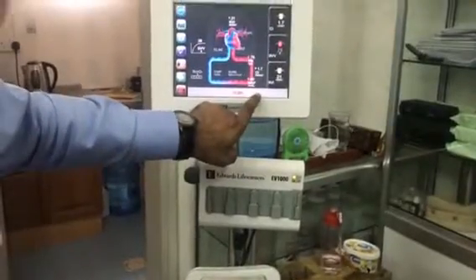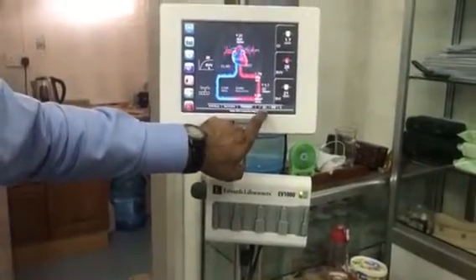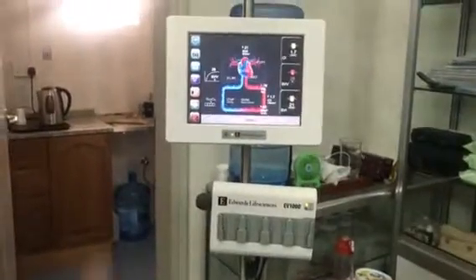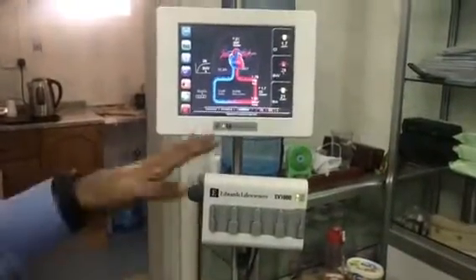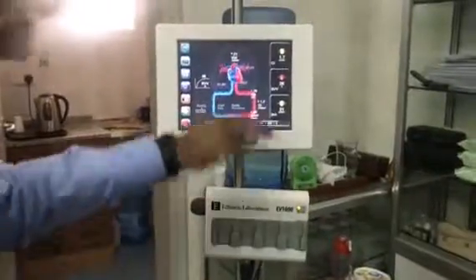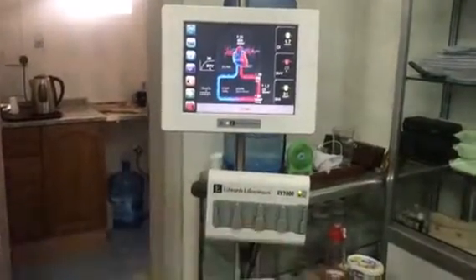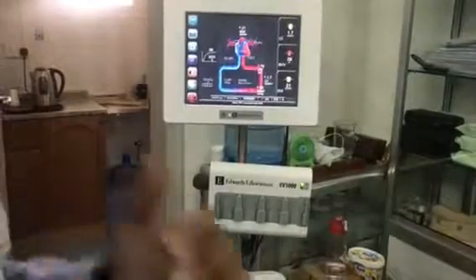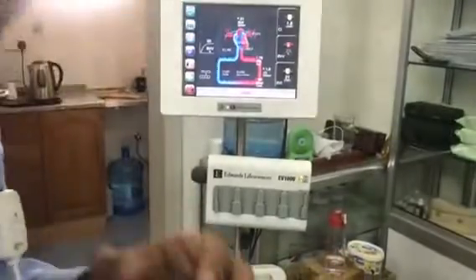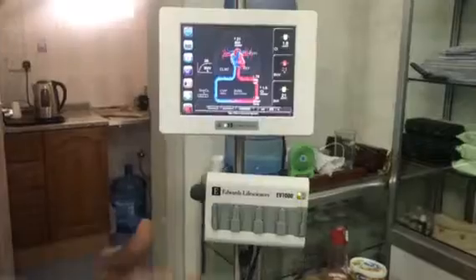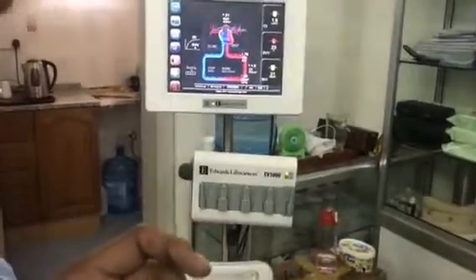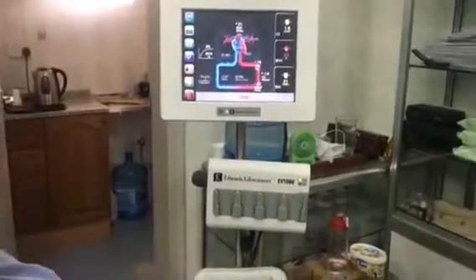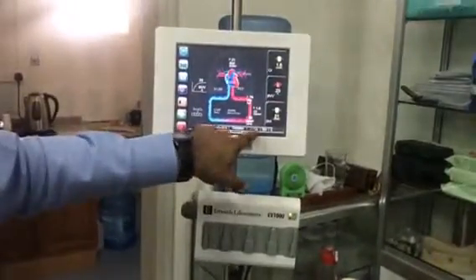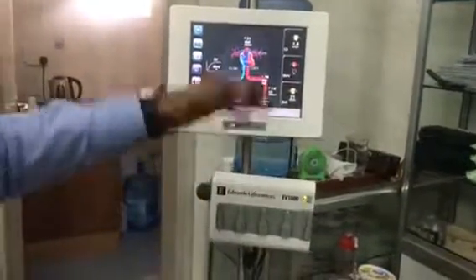Remember, these measurements are always reliable only if this number is above 30. This shows that not much calibration is required. The patient's signal is stable. If it is below 30, it means the measurement is going on but it's not reliable, it's taking time. Maybe there is no perfusion on the finger, or due to some other reasons the value is not being received, or the finger cuff is of the wrong size or not properly placed. So this has to be always above 30. Above 50, much better. Now these are the normal parameters.